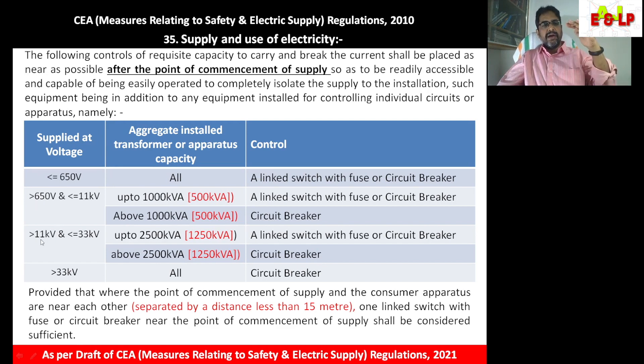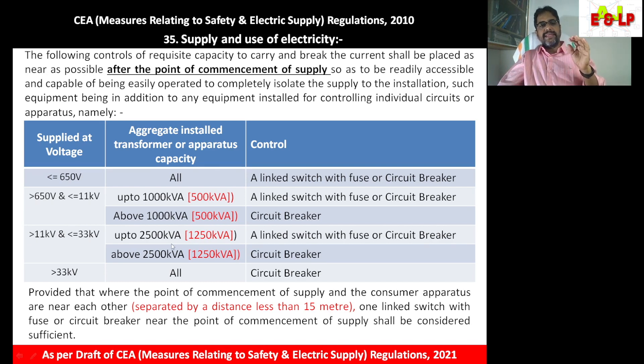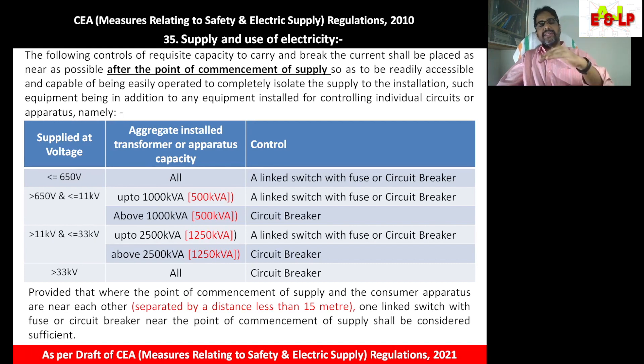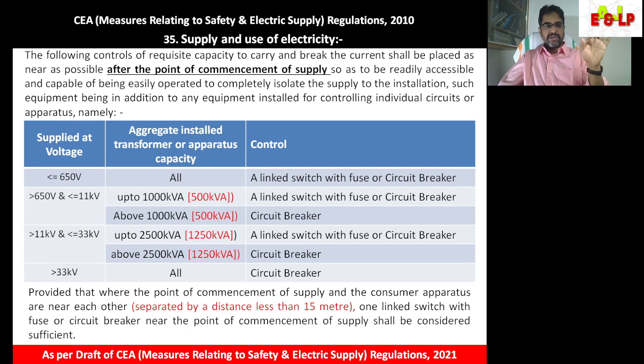The next category: if the voltage is between 11kV and 33kV and the transformer rating is up to 2500 KVA, there can be a linked switch-fuse unit or a circuit breaker. This limit is extended to 2500 KVA because the voltage is higher and current is lower. Above 2500 KVA, a circuit breaker — VCB — is mandatory. If the voltage is above 33kV, a VCB is also mandatory.